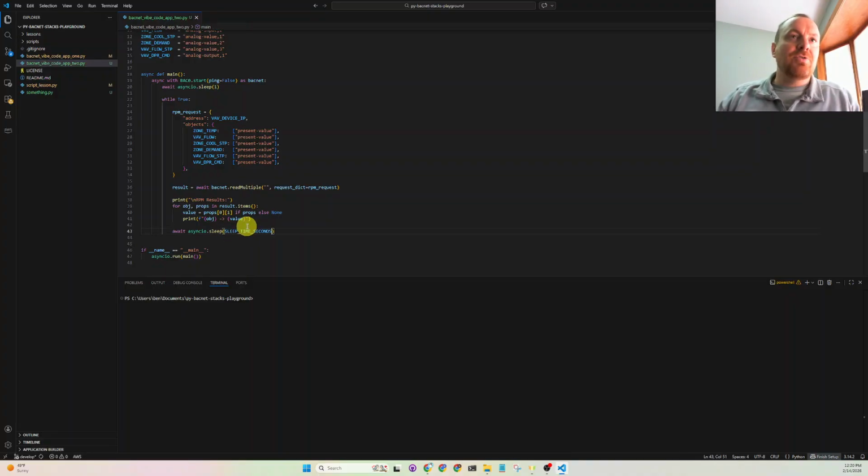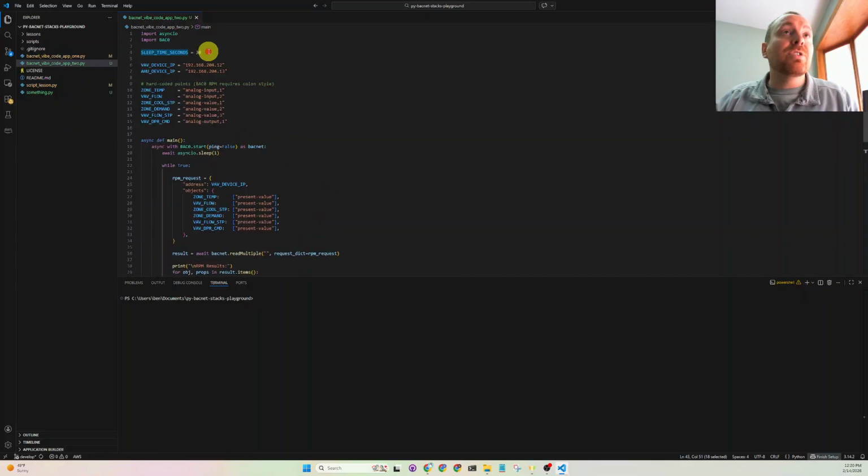I don't think that you'd be doing that in the field that often if you're collecting data for HVAC operations. I've seen research studies where we used to do 60 seconds, and that was even a lot of data. So if you were just scraping data for fun or collecting it, letting it run long term, I would do every 5 minutes or 300 seconds.